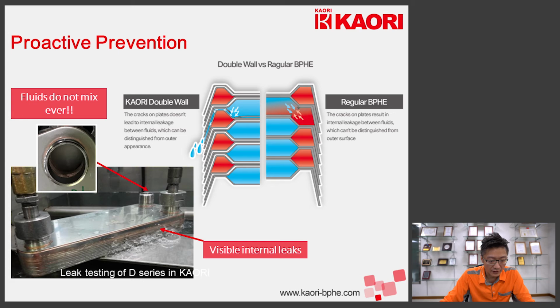Therefore, Kaori developed a double wall technology. Not only does the second layer prevent the fluids from mixing in case the first layer breaks, but there's also a visible leak from outside of the heat exchanger, allowing the end user to replace it with a new unit. The picture below shows a failure in the first layer. The fluid actually leaks from the side of the heat exchanger, but the inside still remains intact and internal leakage does not happen. So how did Kaori achieve this?